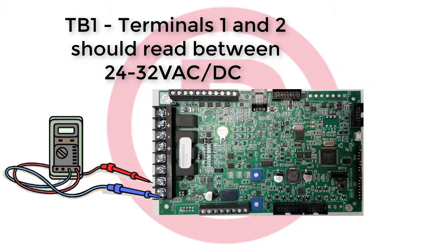You will want to measure the voltage input on the transformer on terminal block 1, terminals 1 and 2, which should read between 24 and 32 volts AC or DC.